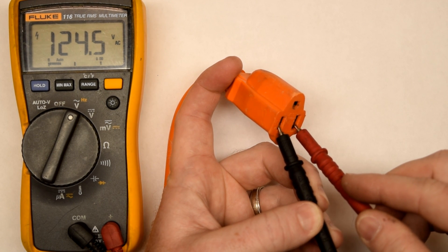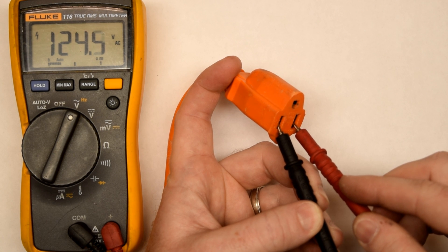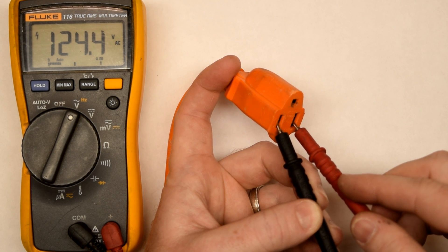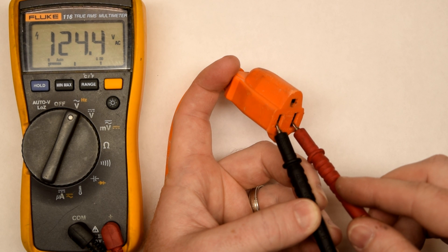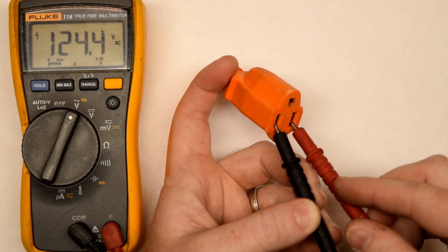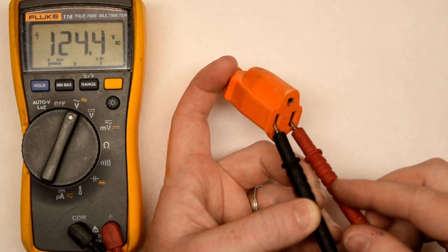And roughly 124 volts. So that's good. Wall outlet should have around 120 unless you're testing a dryer outlet, which should be roughly 220, between 220 and 240 volts AC.